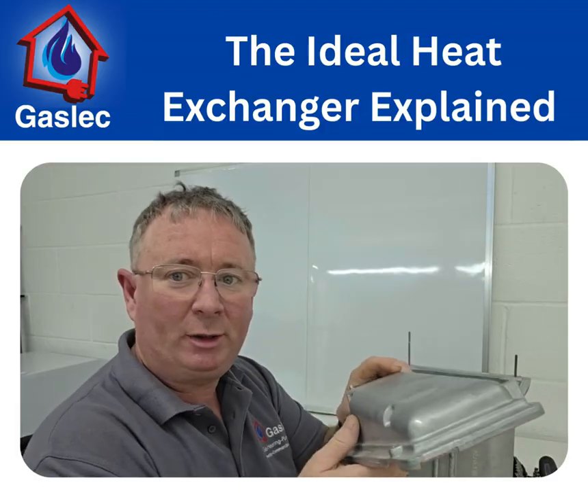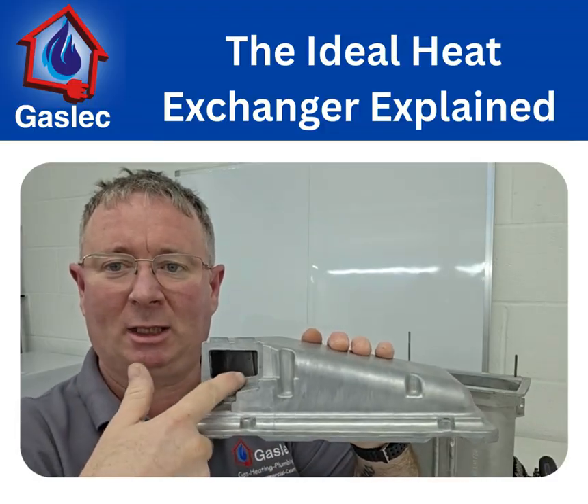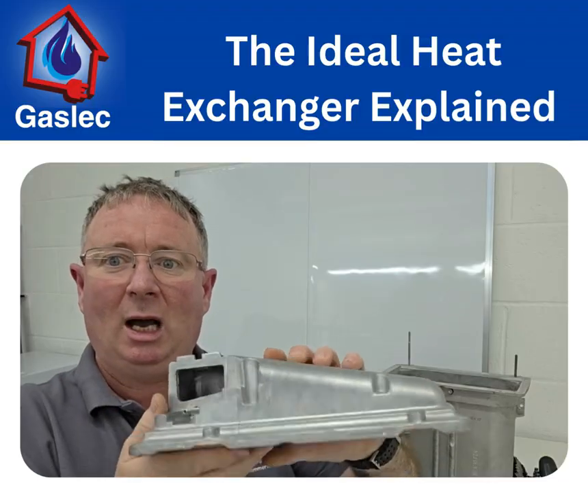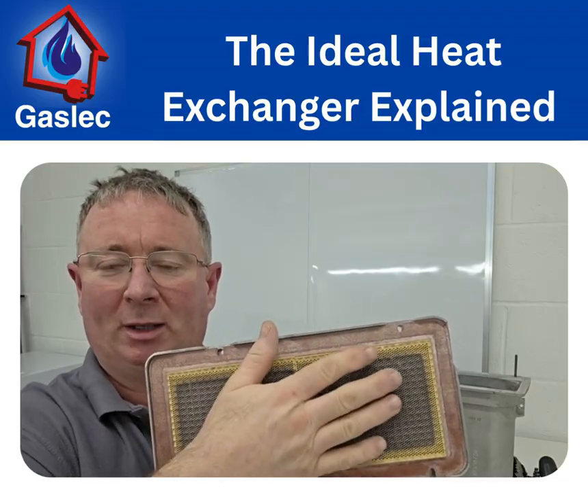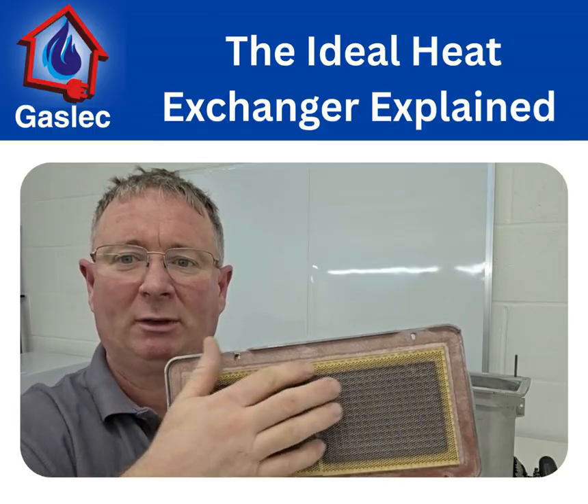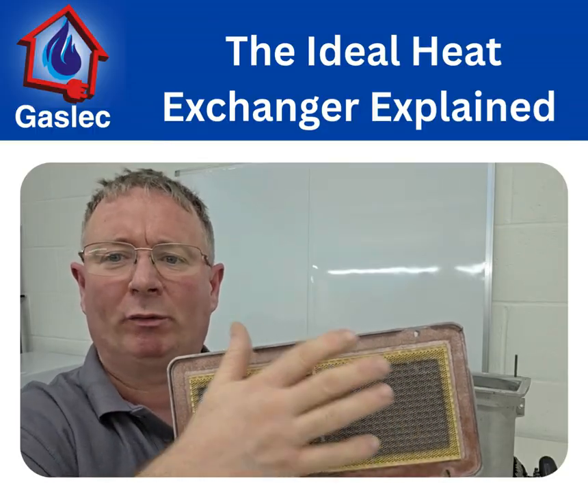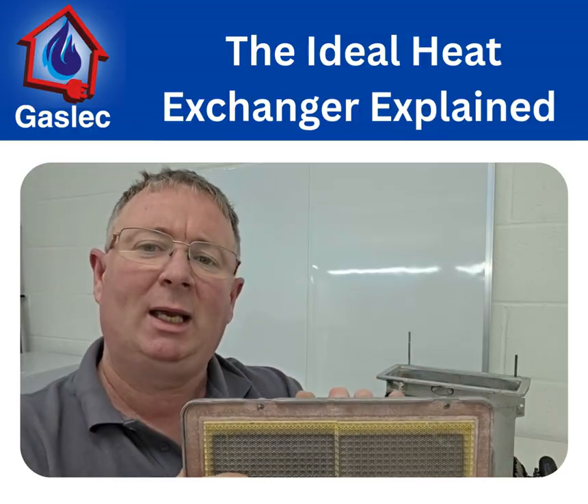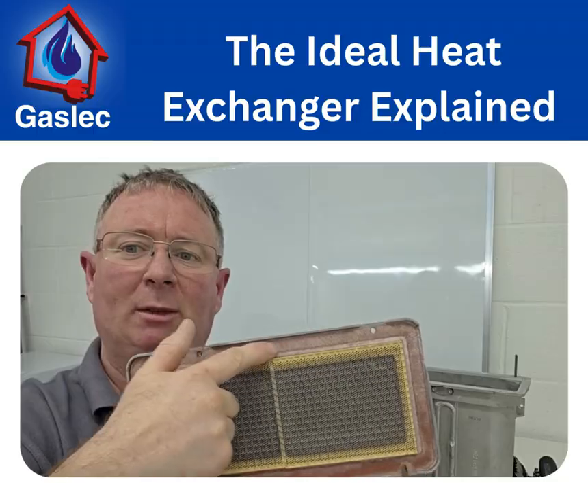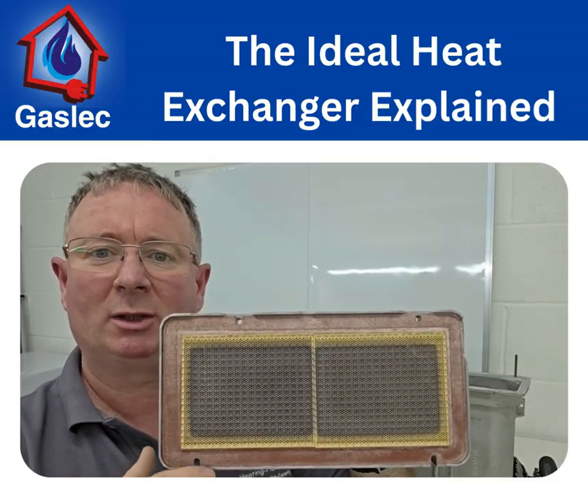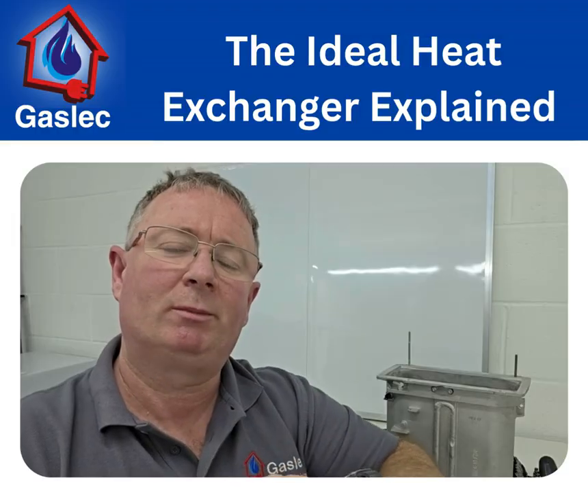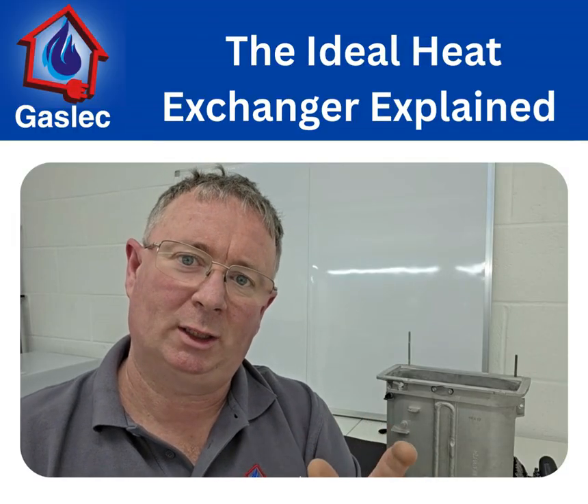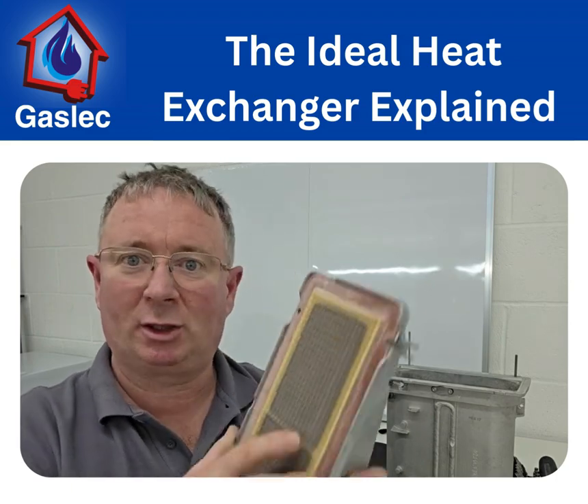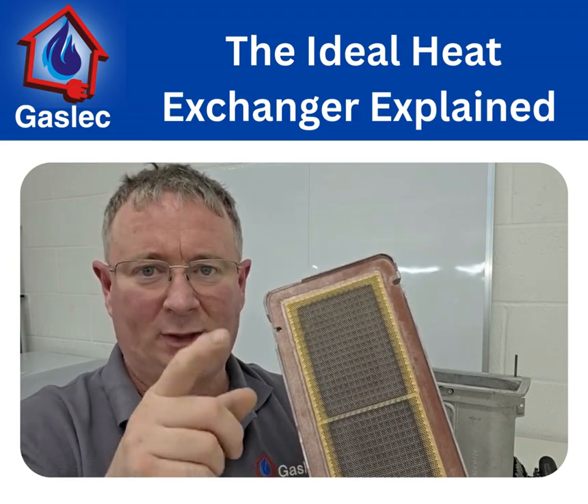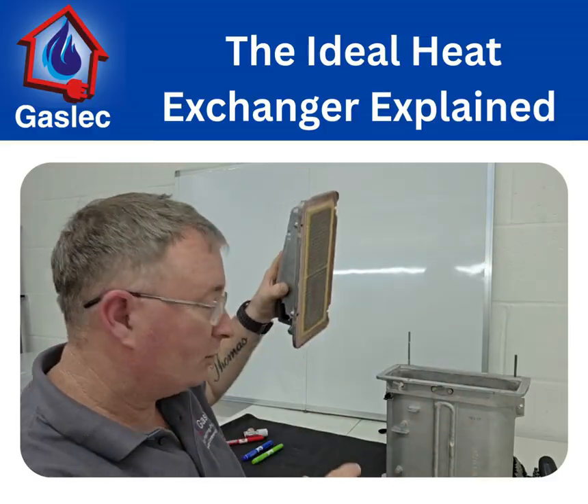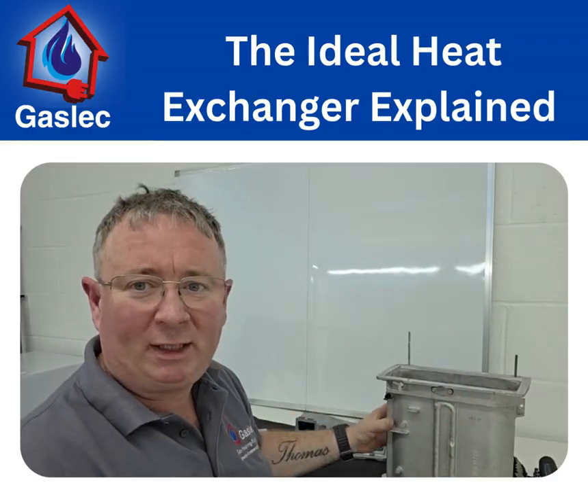So here we have the burner. The air gas mixture comes into this top section and then comes out here at the burner plate. This will give it a nice rectangular sort of flame, downward firing into the heat exchanger. And then we double check this little seal here as well to make sure it's all intact. It is a reusable seal. The Worcester ones aren't on the juniors, but they certainly are on these. So we double check that on the inspection on the boiler service.